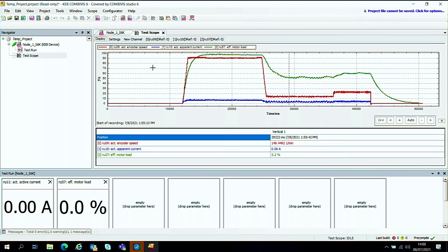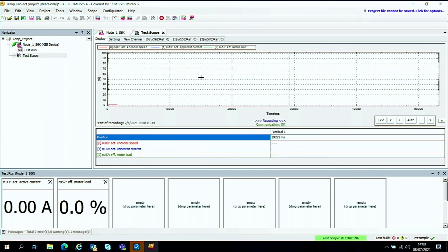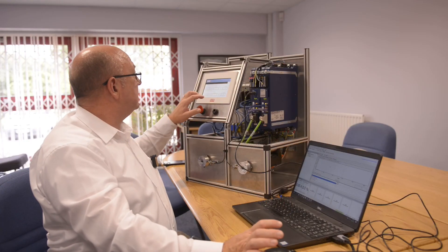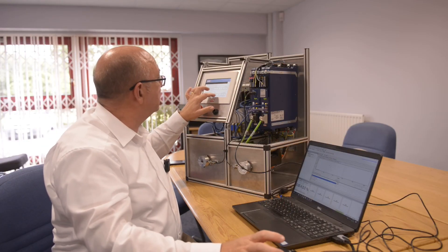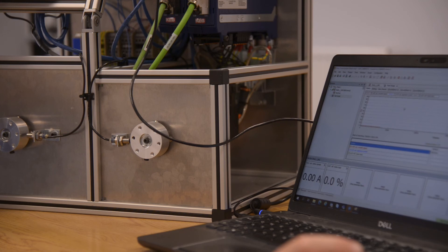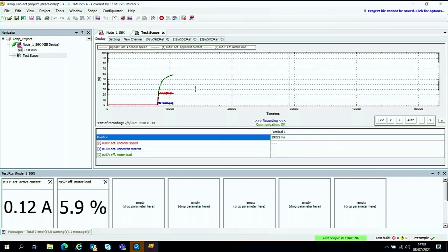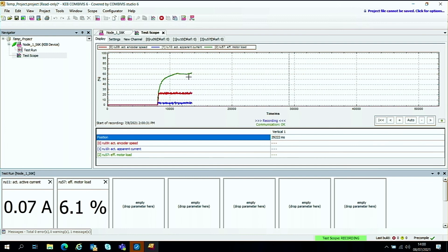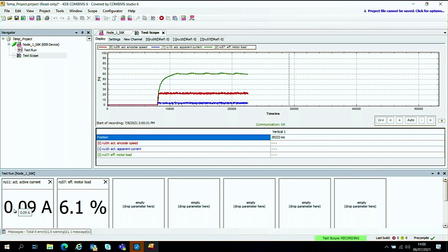And what I'll do now to show you a live, how useful this can be. If we start the scope running as we did before. What I do is I'll now start the motor turning. And you can see the load's now picking up. It must be around about 6% on the scope. We've got a live value in the parameter cockpit down here. And we've also got an idea of the active current.